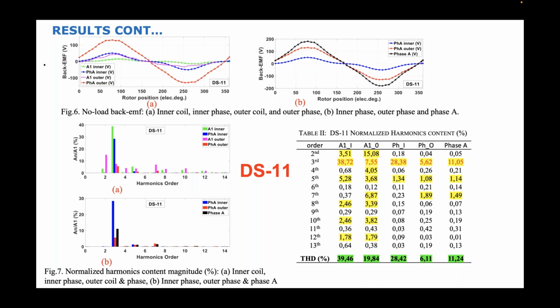Results of 11 rotor pole. Just like in 10 rotor pole, the coil voltage is unsymmetrical, but the phase voltage is symmetrical. But one thing to observe here is that for the 11 rotor pole, the overall phase voltage contains 3rd order harmonics and 5th order harmonics, which is a problem. Total harmonic distortion is reduced just like in 10 rotor pole, but not to the extent of 10 rotor poles. Next slide.